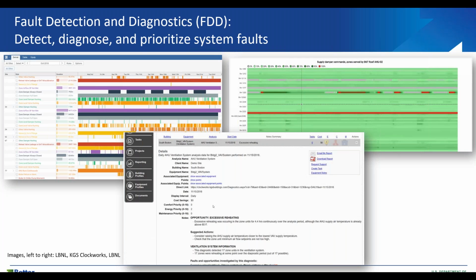The upper right is a diagnostic plot that some FDD tools focus on. It helps the operator see, in this case, which zones the supply air dampers are flat out open—like the red bar there showing a zone that's 100% open all the time—or whether it's oscillating open and closed. These things can really help support the fault summaries available in the tools. Most of these tools have methods for prioritizing faults, which is important because they find a lot of them.